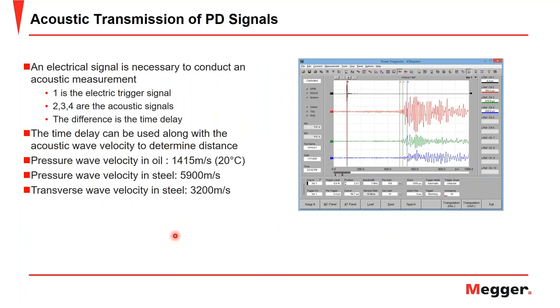But here we have an example of using the acoustic transmission method to locate PD. And when you use the acoustic method, it is necessary to have an electrical trigger. So the electrical trigger is necessary to conduct the acoustic measurement and is seen here in black with the 1. And you can see a time delay between the trigger signal and the acoustic signals that propagate thereafter. And the time delay can be used along with the acoustic wave velocities to determine distance.